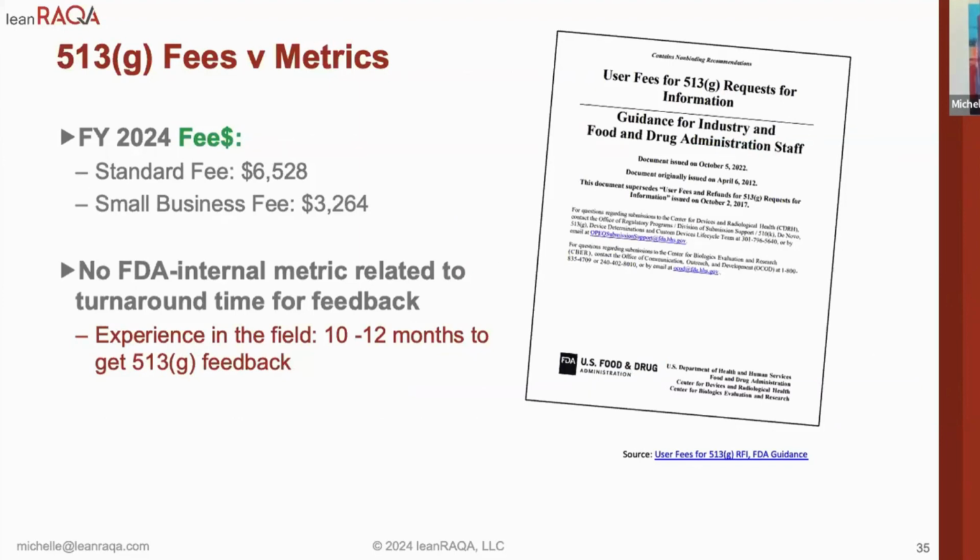However, even though pre-submissions are free, they have a metric associated with them: because of the MDUFA commitments, the FDA gets measured on how often they meet their timelines for the pre-submission commitments. There are no metrics for 513Gs, even though you're paying good money with which they have funding to resource themselves for these reviews.